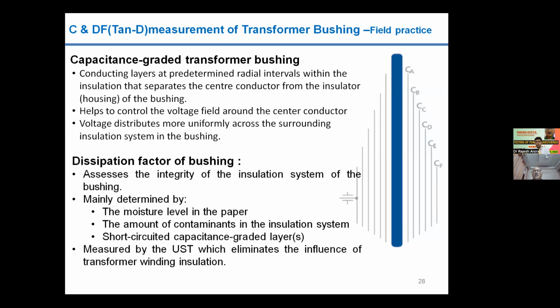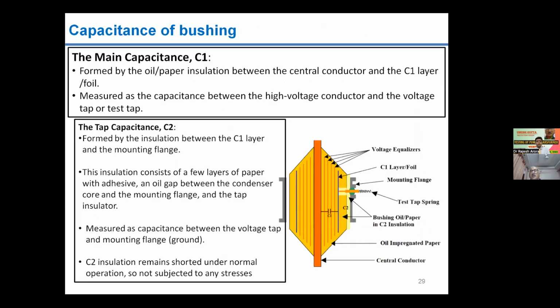C1 is important, and C1 is nothing but the capacitance between the outer layer of this foil, next slide, C1 is the outer paper or outer foil, last, and inside, the rod. So C1 is the indication of the health of the whole bushing insulation, and C2 is basically about the outer foil and the tap, the tap which we take out from the outer foil to earth with the tank.